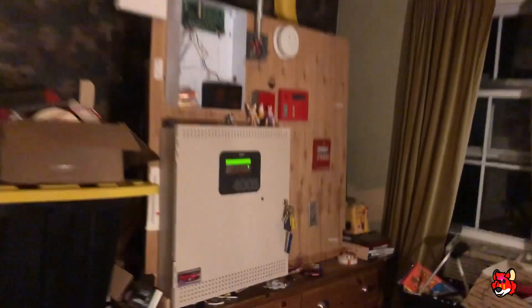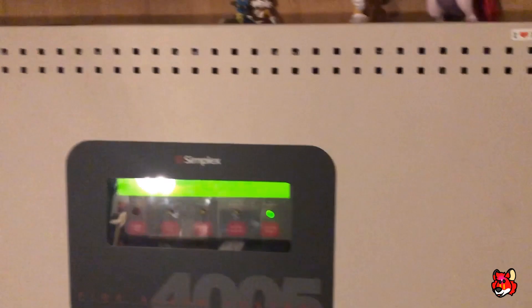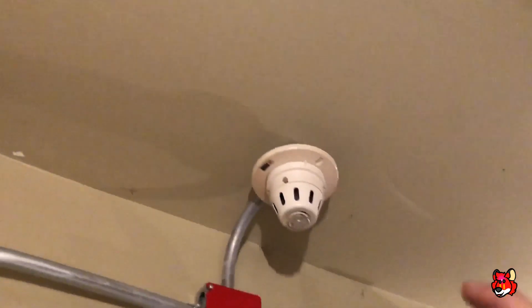We're actually going to start by testing the 9642. I normally don't start off testing smoke detectors, but if you've watched XSkater114 you'll understand why I'm doing it. The system is set on continuous — I will not be doing any other coding option unless requested.